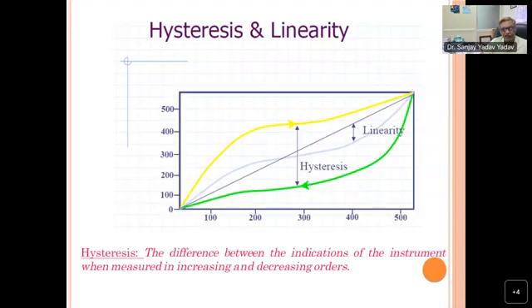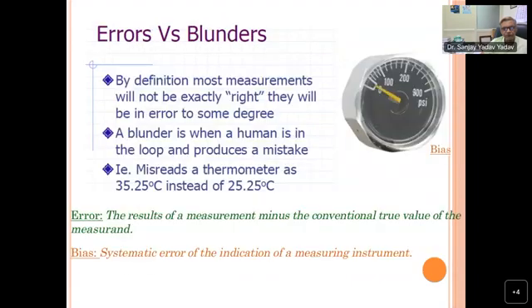Now, if you see this particular graph, in mechanical equipment, when you go by increasing order of pressure and then come back in decreasing order of pressure, there is some value difference, and that differential is normally called hysteresis. This hysteresis is determined using some mathematical formulae, and you have to take this hysteresis value into consideration. So this is the difference between linearity and hysteresis.